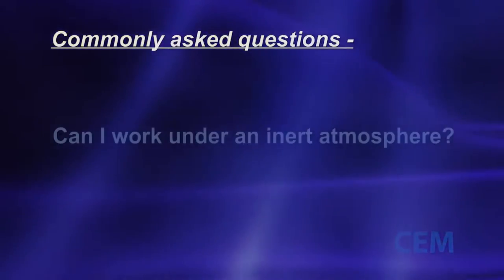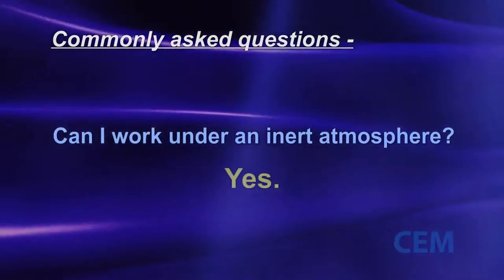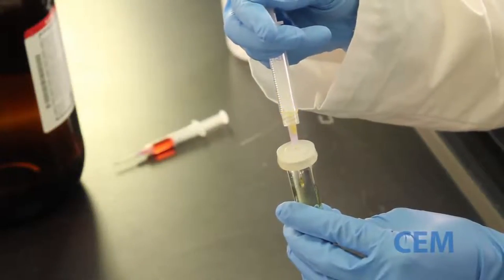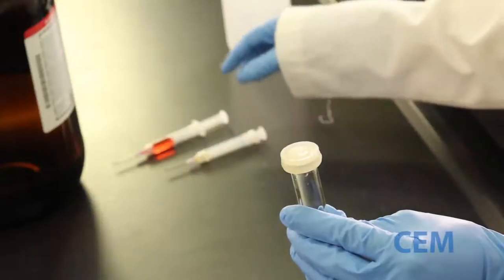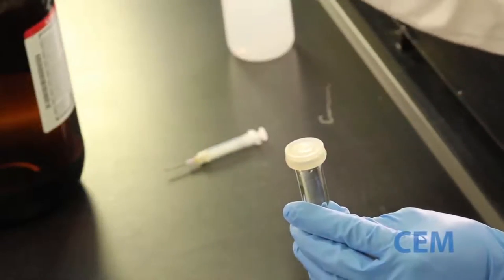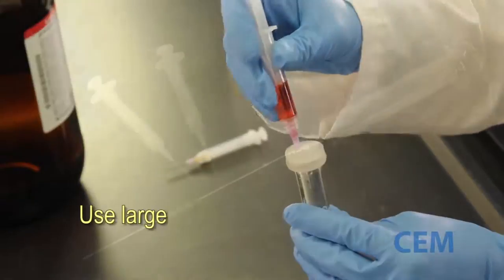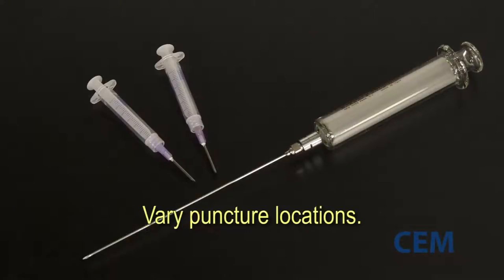Another common question is, can I work under an inert atmosphere? The answer to this question is also yes. The caps used on CEM Discover reaction vials reseal following puncture, as seen here. So inert reactions can be performed with ease. Treat the cap like a traditional septum. Use a larger gauge, smaller bore needle when piercing the cap, and do not repeatedly puncture in the same location, as this could prevent reseal.